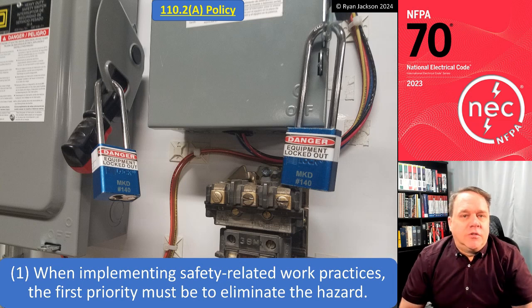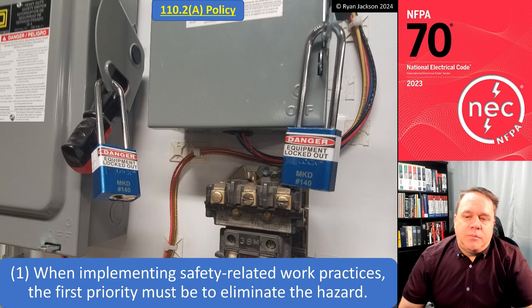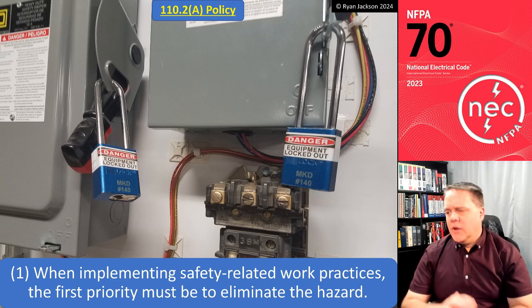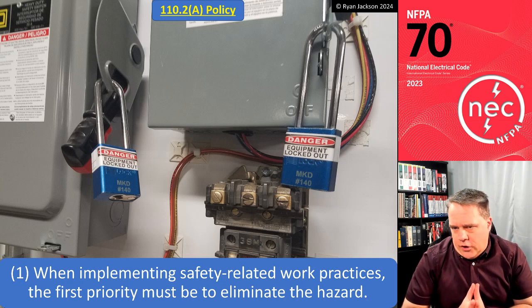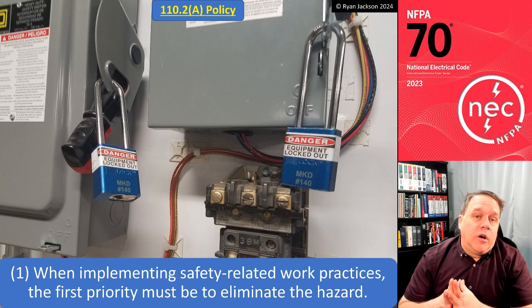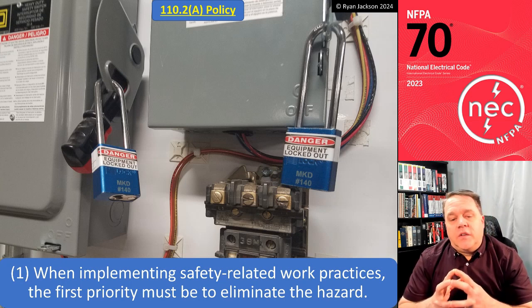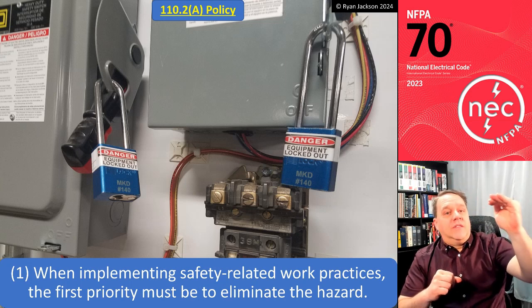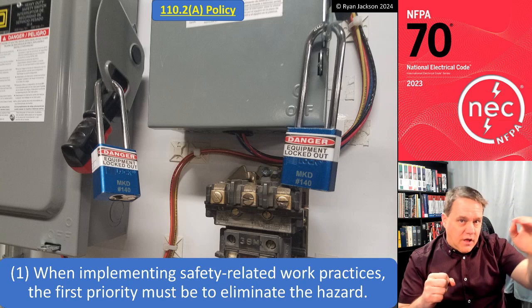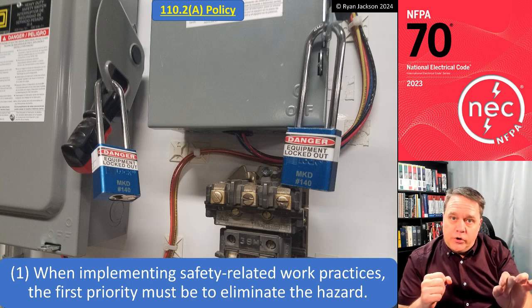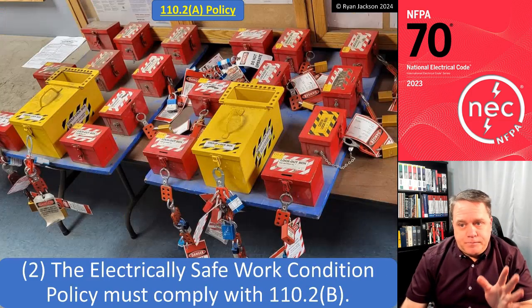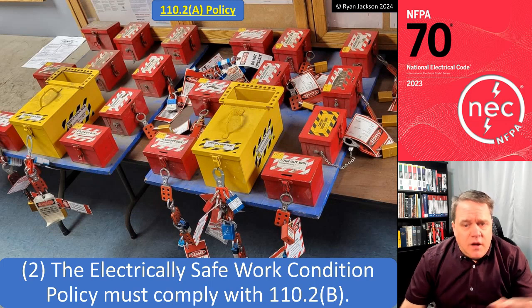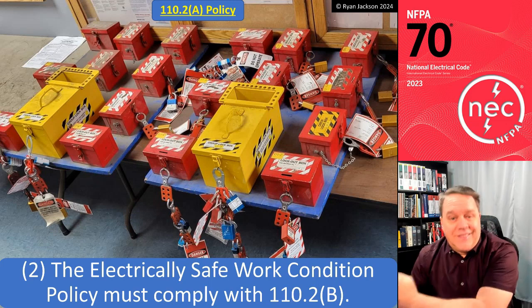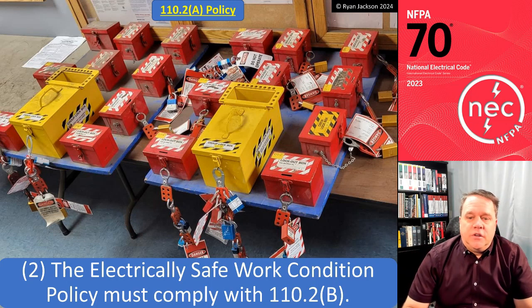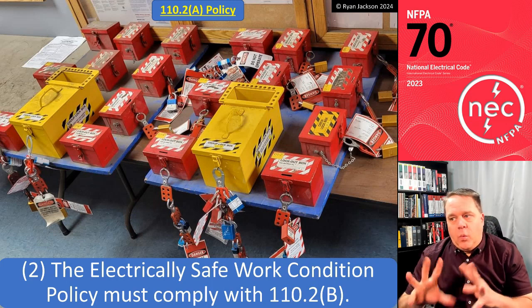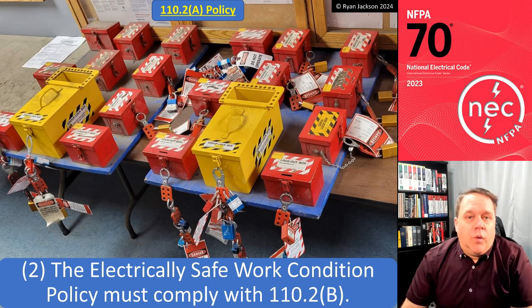When implementing safety-related work practices, the first priority must be to eliminate the hazard. All right, so we have what's called the hierarchy of risk control. And if you're familiar with NFPA 70E, you're probably already familiar with the hierarchy of risk control. That is where we say the first way to establish safety is to eliminate the hazard. If we can't eliminate the hazard, then there's other things that we can do in a particular order. And we're going to talk about that here in just 1 second. The electrically safe work condition policy must comply with 110.2b, and that's what we're going to read next. So A simply says, listen, you need to create a policy. And what needs to be contained in that policy, we're going to talk about in 110.2b.